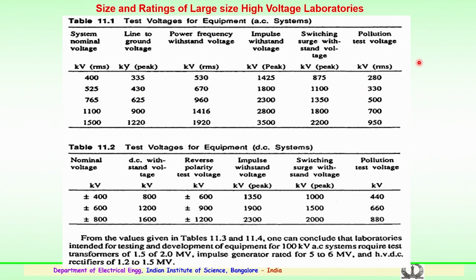So, typical size and rating of large high voltage laboratories, a few of them are shown here. The test voltage of equipment for AC is shown here. The system nominal voltage could be 400, 525, 765, 1100 and 1500 kV. So, the line to ground voltage is indicated here. For 400 it is 335, for 525 it is 430, for 1100 it is 900 and for 1500 it is 1220 kV. So, the power frequency withstand for the components of a 400 kV system has to be 530 kV. In case it is 525 it has to withstand 670, and so on. For 1500 kV, 1920 is the requirement of power frequency withstand voltage.